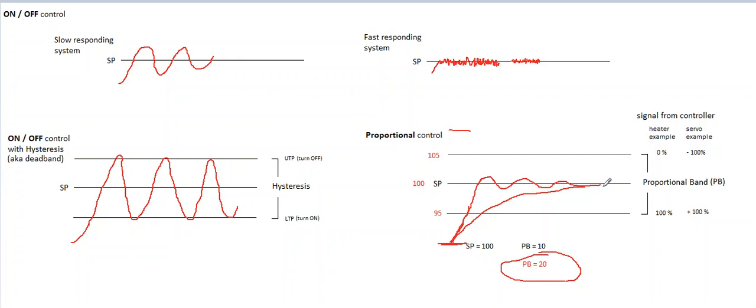One thing to mention, though, is with just proportional control, tuned to not overshoot, you will always have what's known as sag. There's going to be a steady state error, meaning you're never going to get to the set point exactly. And the reason is, to avoid overshoot, you're going to be throttling back like a plane coming in for a landing. And maybe unlike the plane coming in for a landing, it's never going to get to the runway.